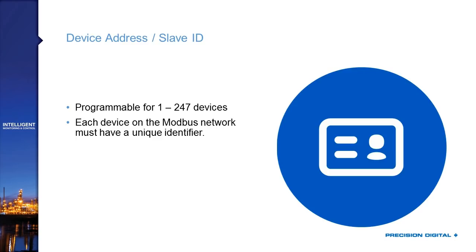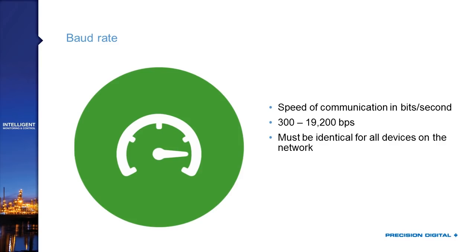Baud rate is the speed of communication. Digital communications always happen in time slices — checking whether it's a one or zero on the line. If those time slices aren't synchronized across everything on the network, communication will fail. All devices need to be reading at the same speed to read those ones and zeros — that's what baud rate is. You'll usually see values between 300 and 19,200 baud. In most process applications speed isn't critical, and most things operate around 9,600 baud.